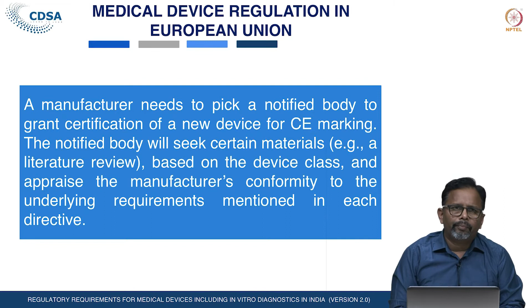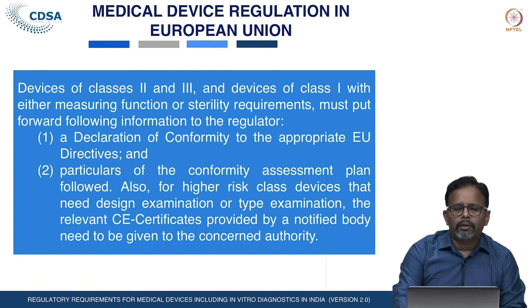Class 2, class 3 and certain devices of class 1 require scrutiny of the application by the notified body. They must forward certain information to the regulator, that is the declaration of conformity to the appropriate European Union directives and the particulars of the conformity assessment plan. Also for high risk devices, that is class 3 devices, they need a design examination or type examination, or the relevant CE certificate provided by the notified body, to be given to the concerned national regulatory authority of that European Union country. In Europe, the notified bodies are private agencies that enact regulatory control over medical devices in the European Union. These notified bodies have the authority to grant the CE certificate for medical devices to the manufacturers.